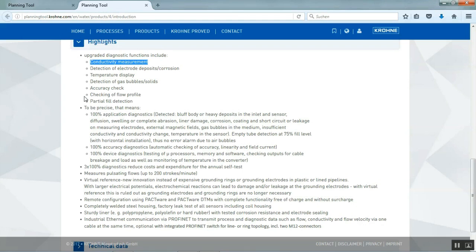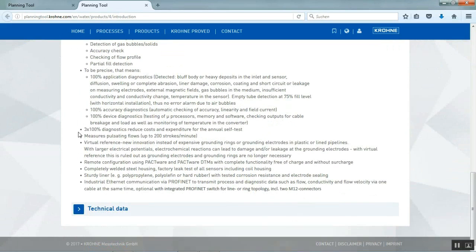So another very, very nice important highlight for this universal version is the virtual reference, which is a new innovative grounding method. Normally, coming from the measuring principle of an EMF, you need to ground the medium before and after the EMF, because you just want to measure the induced signal which was induced in your measuring device.